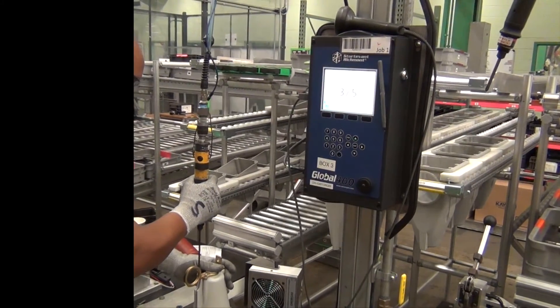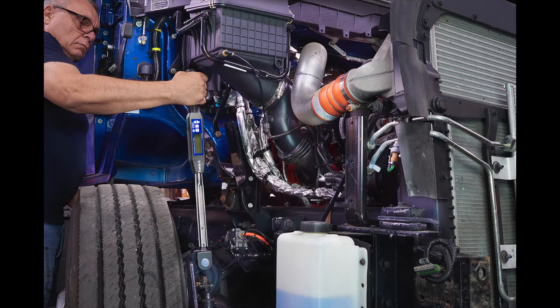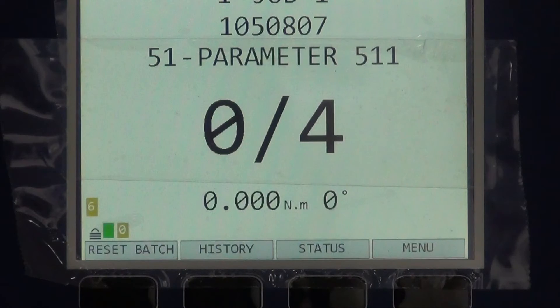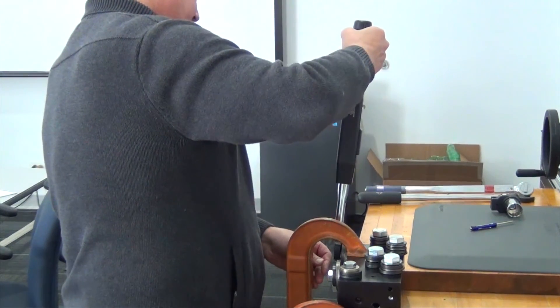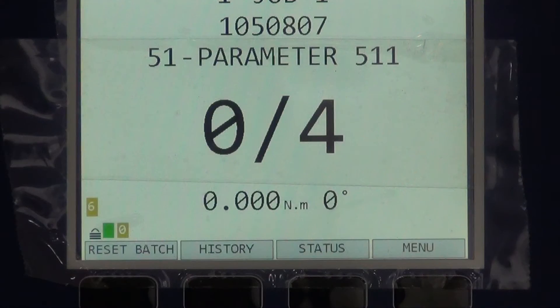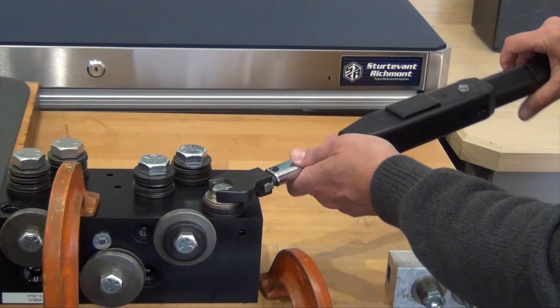The pull-to-green technology found in the 1200 and the 1250 series Xacta 2 wrenches is controlled at the Global 400. The Global 400 is also torque and angle enabled. Using the 1250 Xacta series digital torque and angle wrench, operators can work in three different torque and angle modes: torque to angle, torque and angle monitoring, and prevailing torque mode.